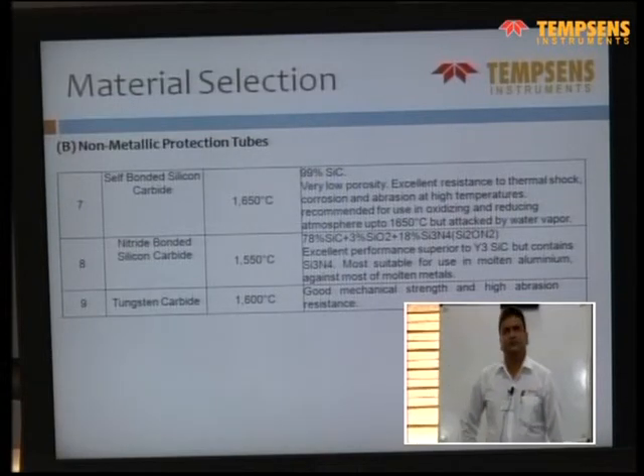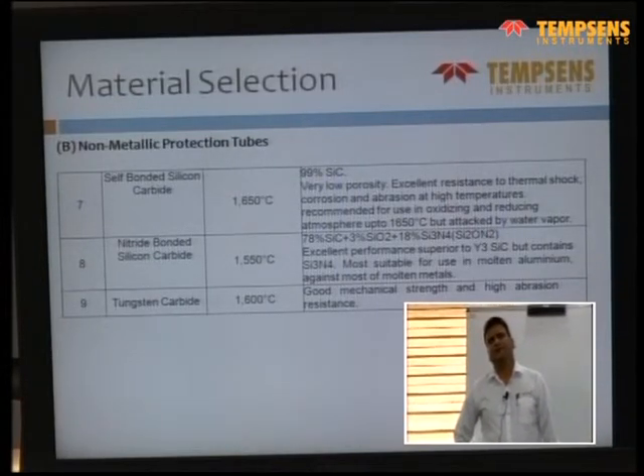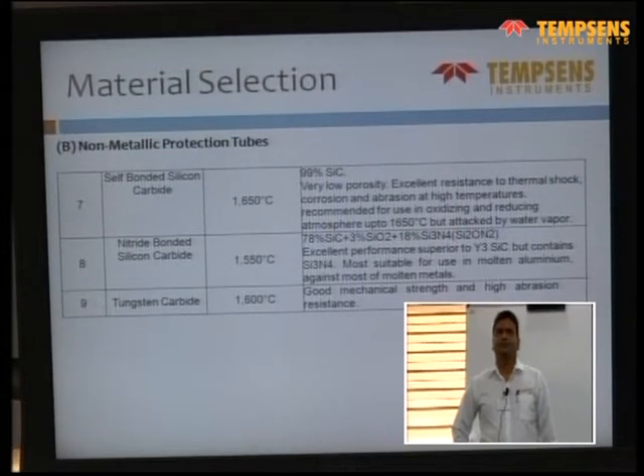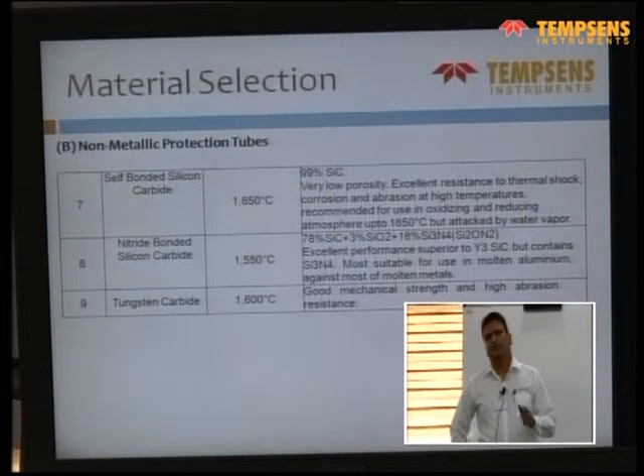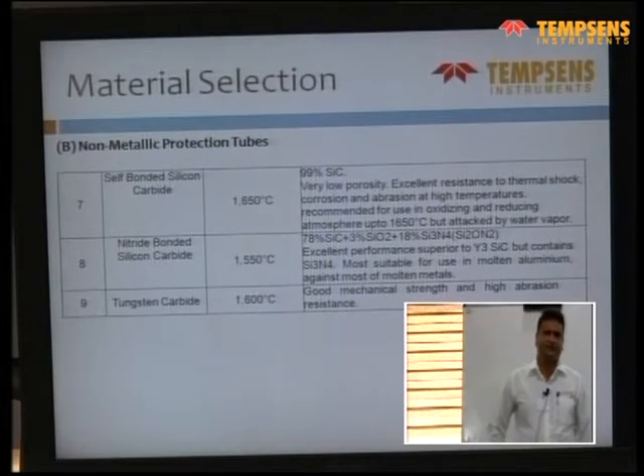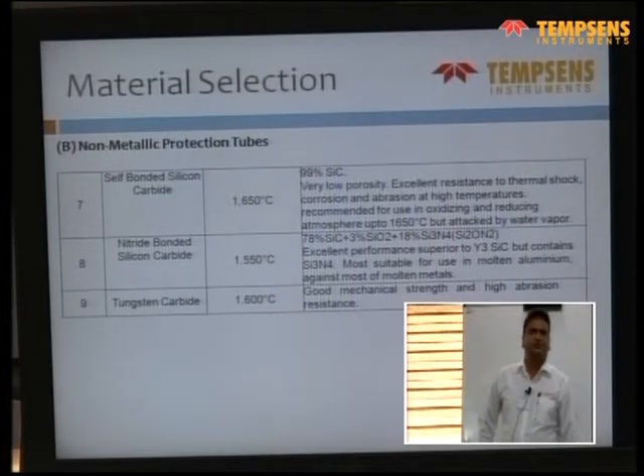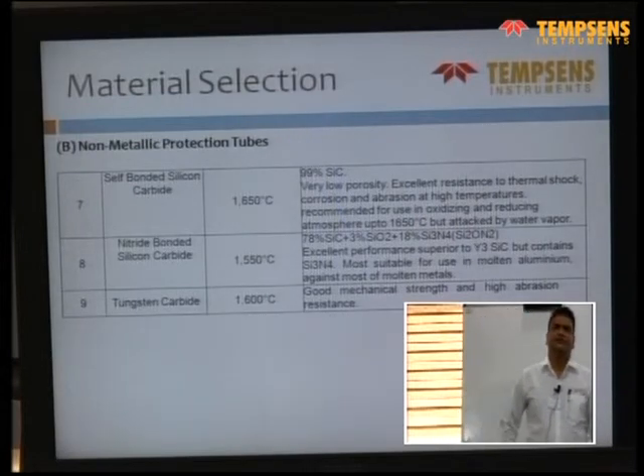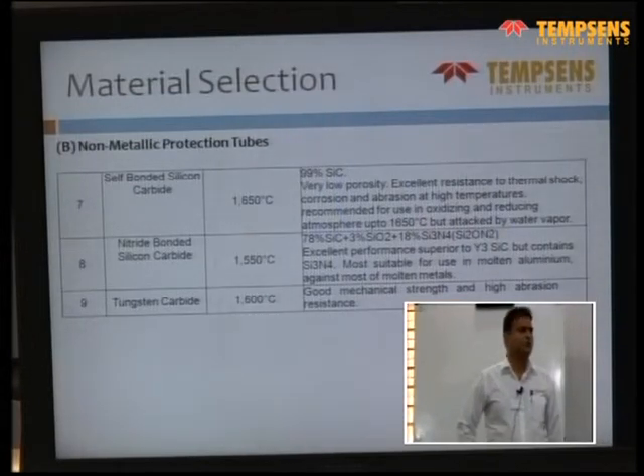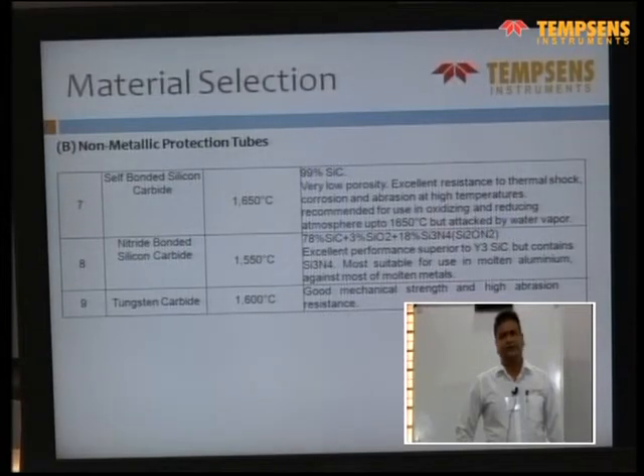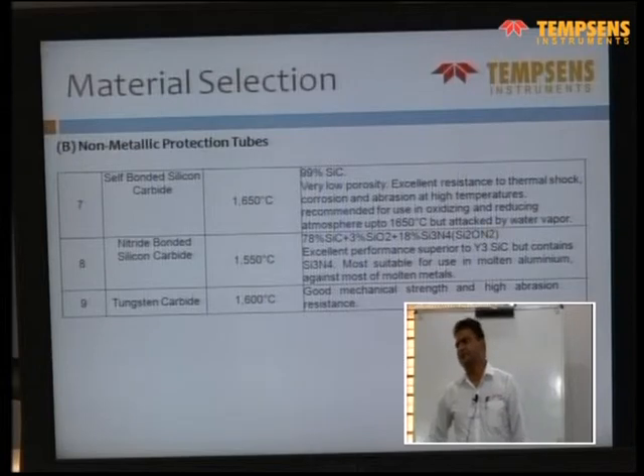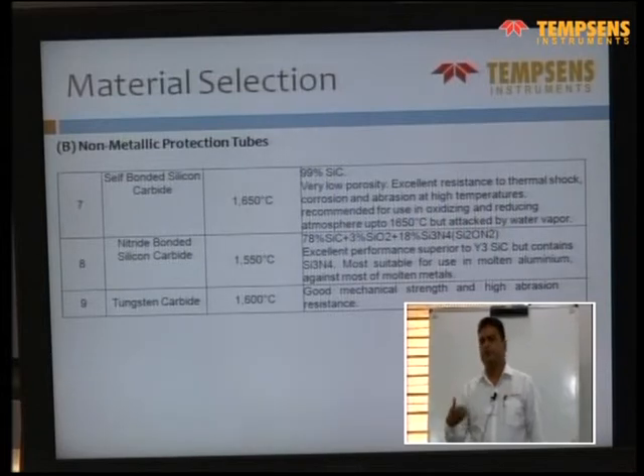There are some other non-metallic tubes, like silicon carbide, which is available in self-bonded or nitride bonded. They are suitable up to 1500 degrees centigrade. They are used in some steel plants, and also for non-ferrous applications. Tungsten carbide's temperature range is not 1600, it is actually less than that, but it is a very hard material. It is used for coal mill applications. So in a power plant, solid sintered tungsten carbide thermowells are used, which can give a good life in a coal mill application.